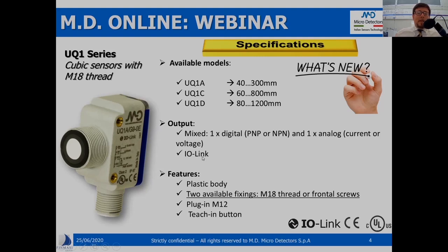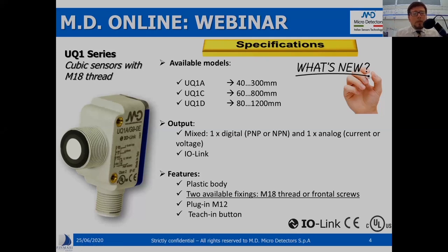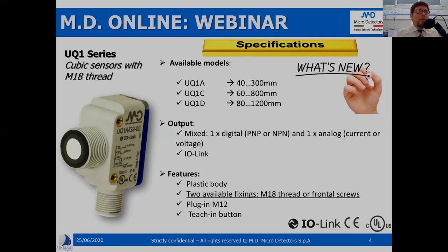Another way of clustering UQ1 products is based on the possible output. We have to distinguish between the standard product with standard communication mode and the models with IO-Link communication. Regarding the standard models, they have a mixed output — both a digital output, PNP or NPN, and an analog one, either current from 4 to 20 mA or voltage from 0 to 10 volts.